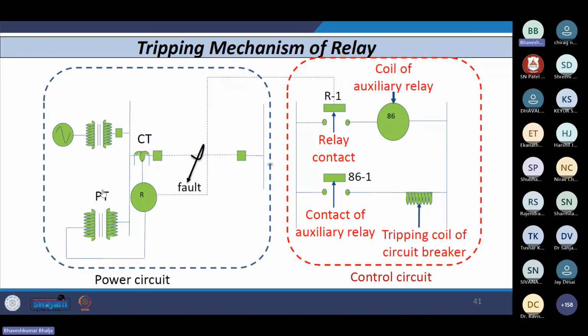Reclaim time is usually decided based on this: we know that whenever a fault occurs and the breaker contacts separate, then inside the breaker, depending upon the type of circuit breaker we use, let's say we use an SF6 circuit breaker, or let's say we use a vacuum circuit breaker, depending upon the type of breaker, the arc quenching medium is there. And you have also studied at UG level that there are arc quenching theories. There are two main theories which we have studied. One is Slepian's theory and another is Cassie's theory.